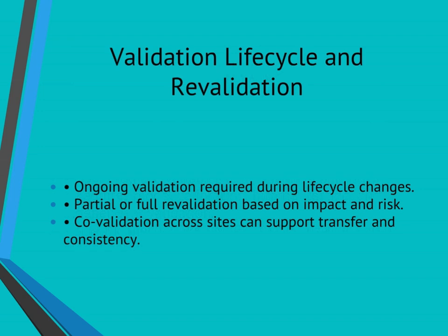Validation is no longer a one-time event. It continues across the method's lifecycle. Revalidation may be required following method changes, lab transfers, or new equipment introduction. The extent of revalidation depends on the risk and impact of the change. Q2(R2) supports partial, full, or co-validation strategies. Co-validation across multiple sites can serve both as validation and technology transfer, helping standardize analytical procedures globally across an organization's network.